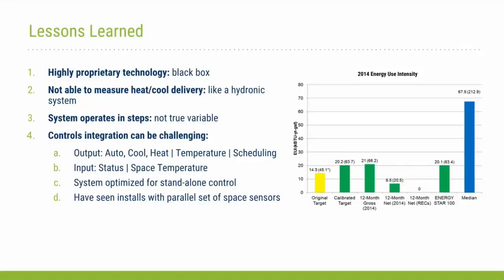So for example, during cooling, being between 75 to 78, for heating between 69 and 72, initially we had to have a wider range in the installation. The system really is optimized for standalone control. So when these are installed, we're just using wall-mounted thermostats and maybe a manufacturer-provided touchscreen panel. They work very well, and they tend to be fairly easy to commission. It is, again, when you're using that building automation system that doing everything you want it to do can be challenging.